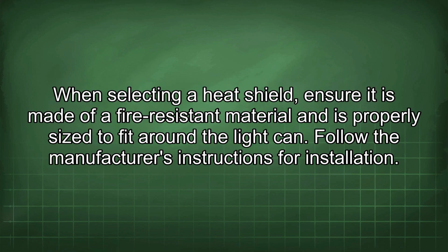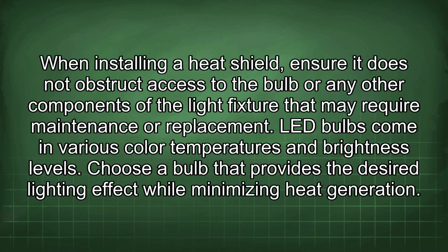When selecting a heat shield, ensure it is made of a fire-resistant material and is properly sized to fit around the light can. Follow the manufacturer's instructions for installation. When installing a heat shield, ensure it does not obstruct access to the bulb or any other components of the light fixture that may require maintenance or replacement.